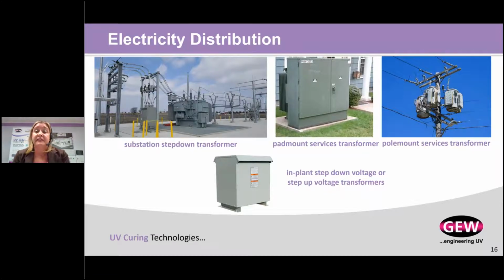It's important to understand because we don't always think about it in the US, but when we talk to customers in Latin America, the issue often raised is that they don't have the ability to pull more power off the line. Those transformers have a rating, a max power rating. Once your plant exceeds the power coming into your facility, you either need to add another transformer and work with the utility to put that transformer on the line. If the grid and the plant supplying that line doesn't have excess capacity, it becomes very difficult.